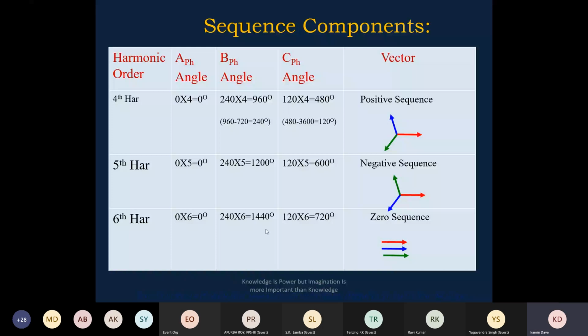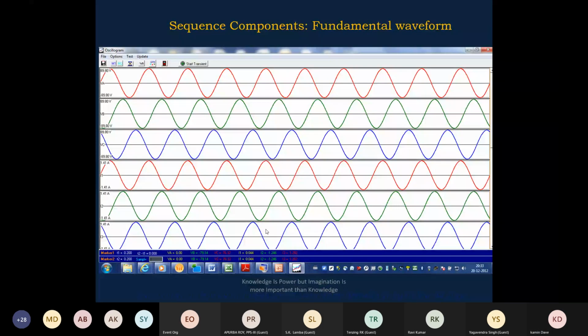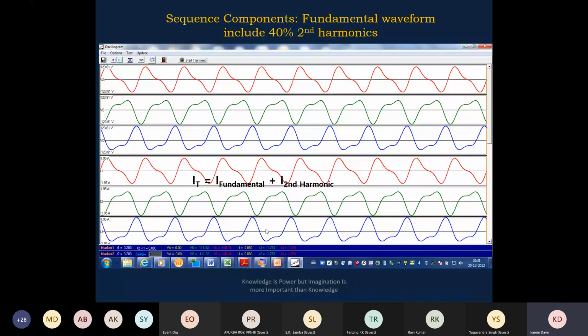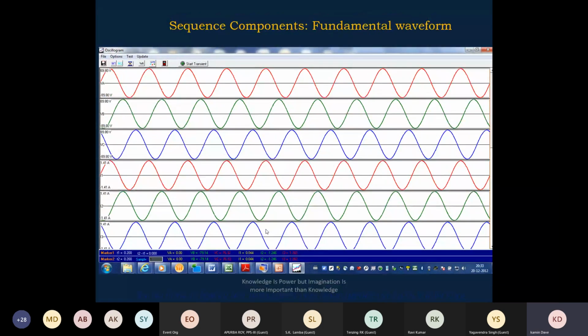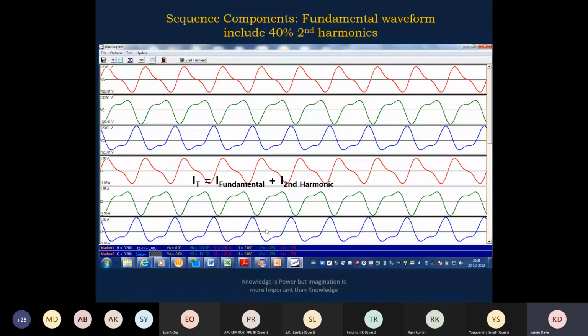Sixth harmonic zero sequence. Seventh harmonic, again positive sequence. So positive, negative, zero, positive, negative, zero. That is how you look at it here. Okay, so you look at it, the fundamental component, the waveform is such a way like this, then 40% second harmonic is added, the waveform gets distorted. You look at it here, fundamental waveform here, and this is second harmonic, 40%. The waveform gets distorted.